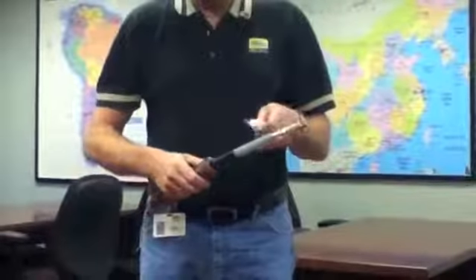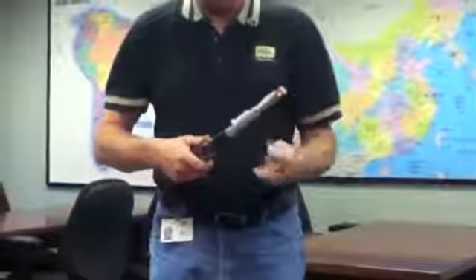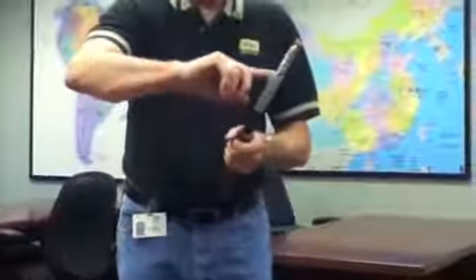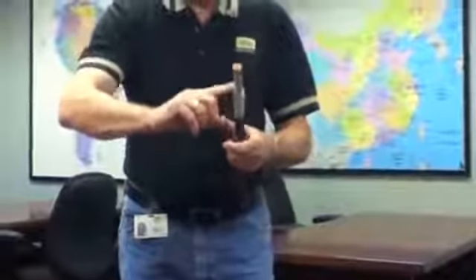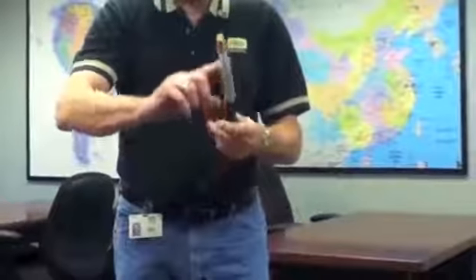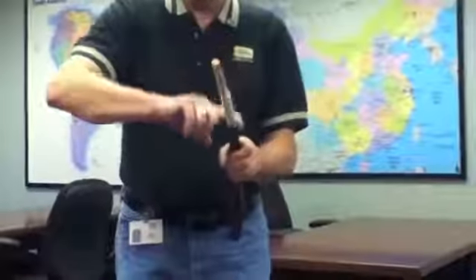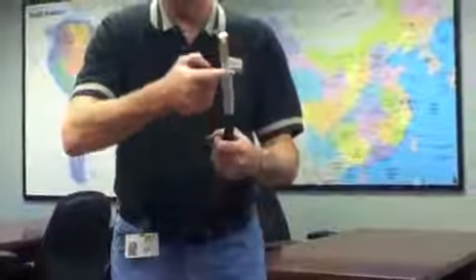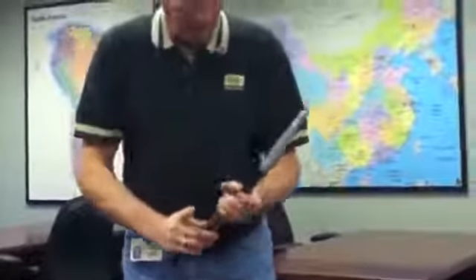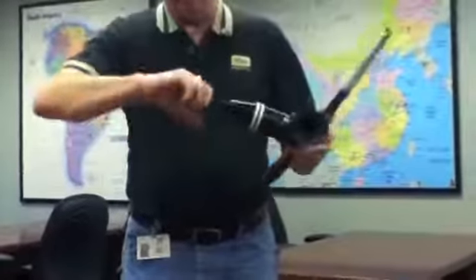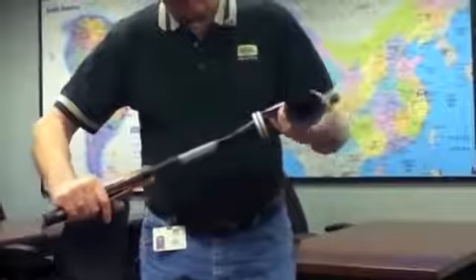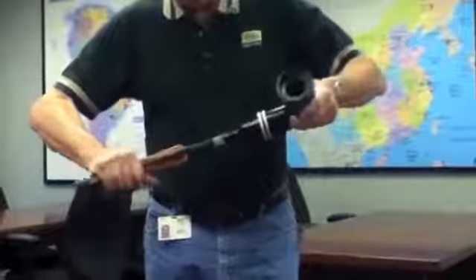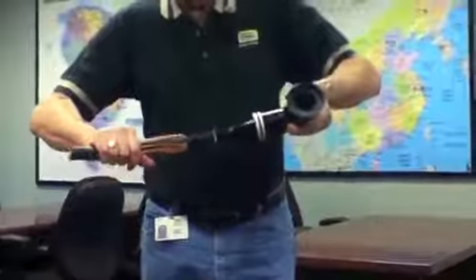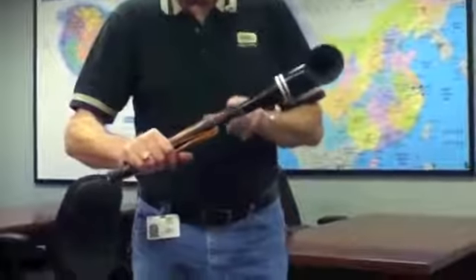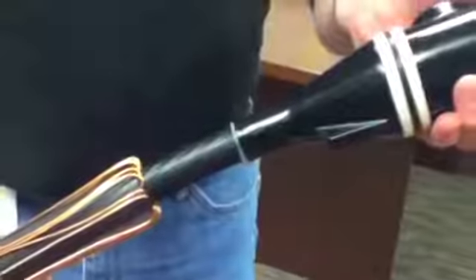Proper application of lubricant is to apply a thin film across the entire surface of the cable insulation. There's no need to put it onto the contact, but you definitely want to make sure that the entire insulation is coated with a thin film. Also, you want to apply some lubricant to the inside or bore of the housing. Now we'll try assembly again, and this time with lubricant there is less resistance, but it's still more difficult because that lubricant has been pushed, or snowplowed, off of the end of the cable.